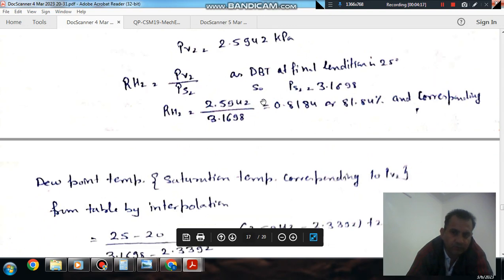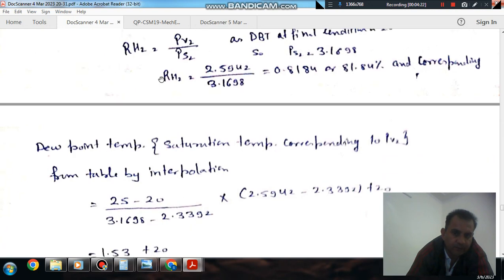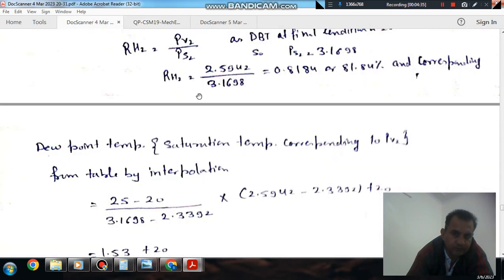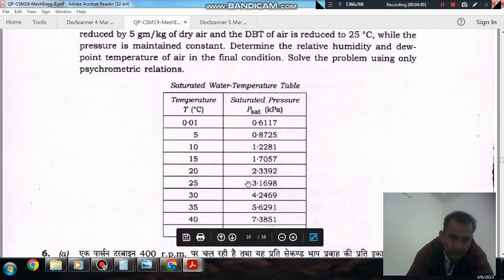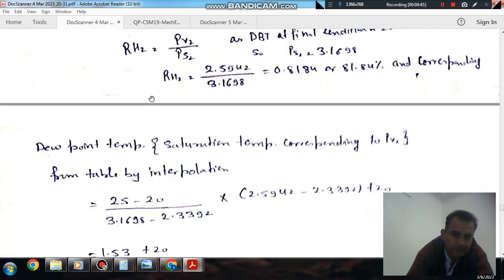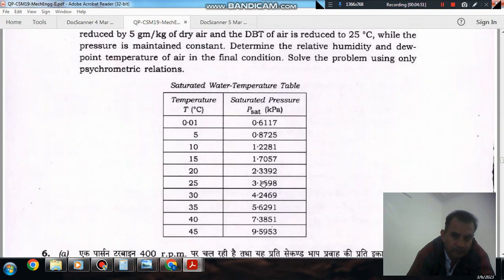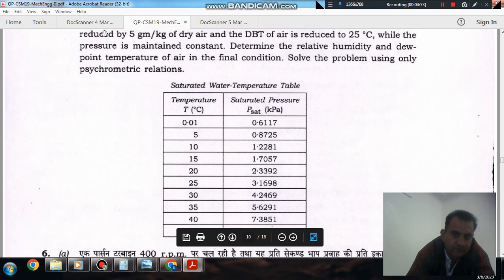And corresponding to this PV2, 2.594 kPa, you can find out dew point temperature. So, as in the table, the dew point for this pressure PV2 is 2.59, so it is lying between 20 and 25 degrees. So by interpolation, the difference of temperature is 5 and the difference of saturation pressure is this much.